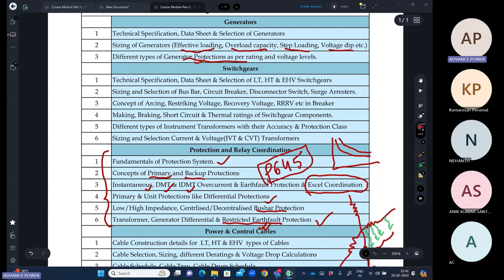So before this protection I have just explained, definitely for protection we need switchgears. So in switchgears we have bus bar, we have the circuit breakers, we have the disconnector switch, we have the surge arresters, and a very important parameter is the CT and PT, which will be sensing equipment for operating the relay and finally the breakers.